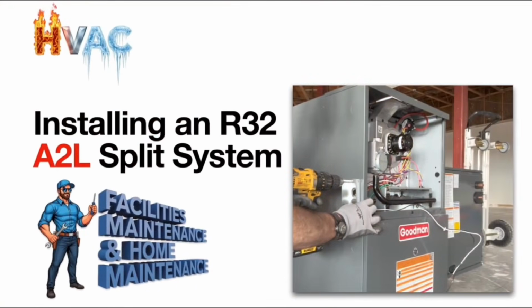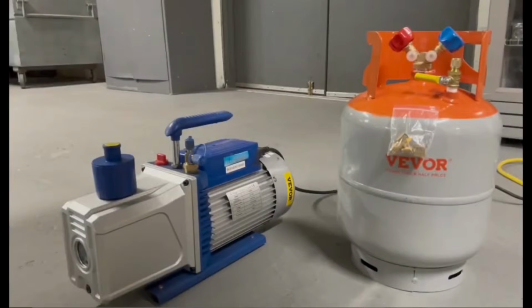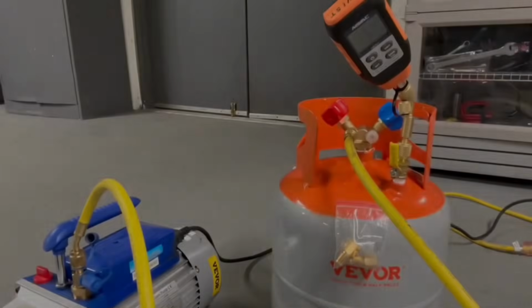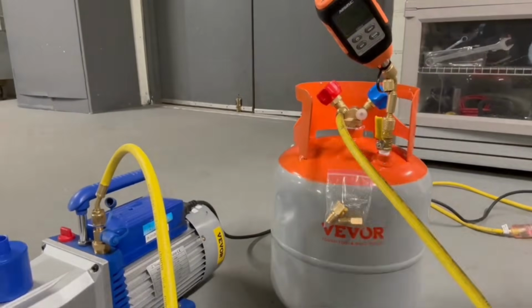Okay, today we're installing an R32 A2L split system. So the unit we're replacing is a 40-year-old R22 system. Before I can recover the refrigerant out, I need to pull a vacuum on my new recovery tank here. Now I need to hoist everything up on the roof, all my tools and supplies.